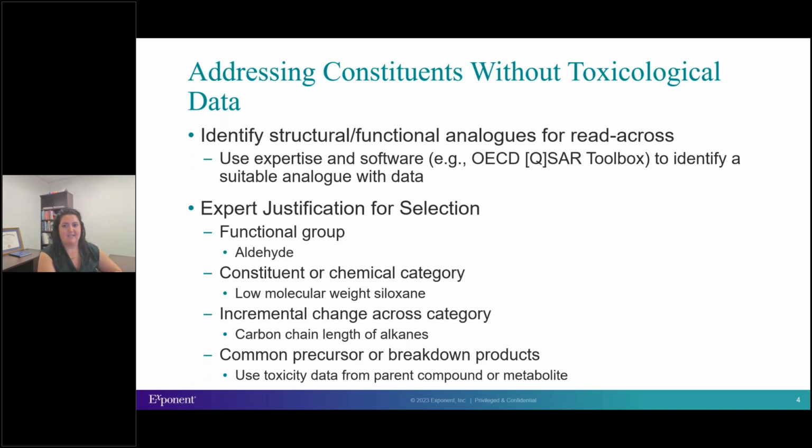So even though the identified constituents are likely fragments of Irganox 1010, to be extra conservative, we'll rely on toxicity data for the more potent compound BHT for read across. But in our justification, we can provide additional context in the TRA that this surrogate selection is likely overly conservative and that the constituents are likely fragments of the Irganox 1010.